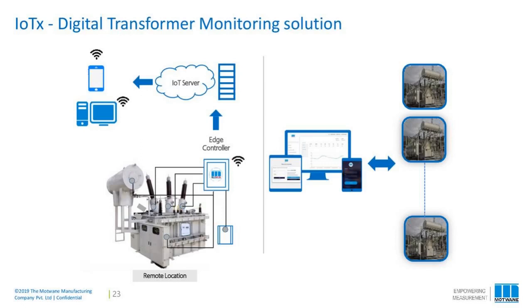Provided, of course, the right signal output is available, which in this case is a 4-20 milliamp output. If that's not available, or the OTI and WTI are not of the hybrid type, then yes, you would need to replace those sensors, but those are very easily available from some of the leading OTI/WTI sensor manufacturers, and we work with them closely. So we can always work together to find a suitable replacement.